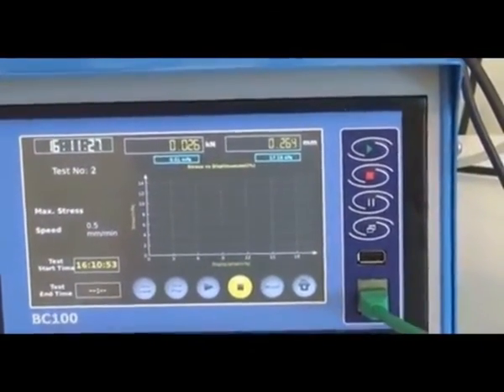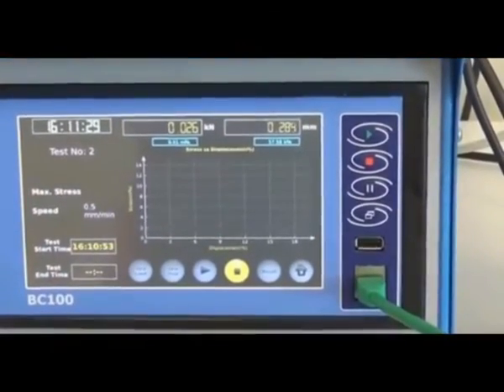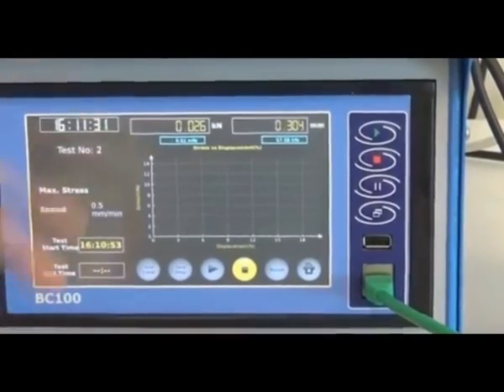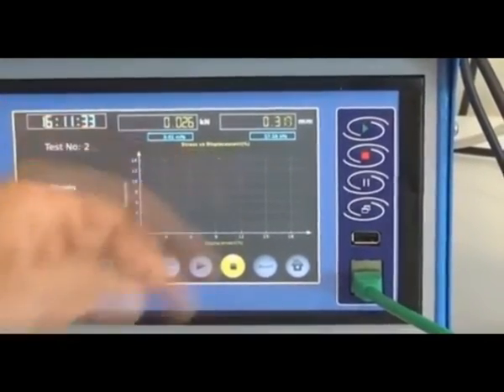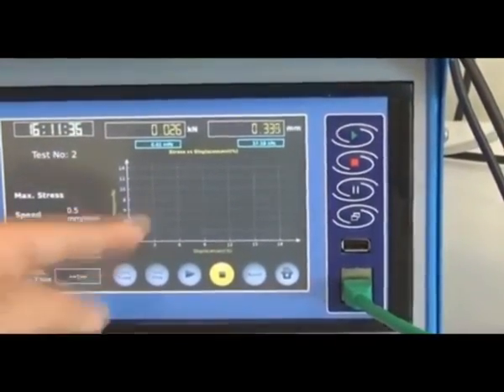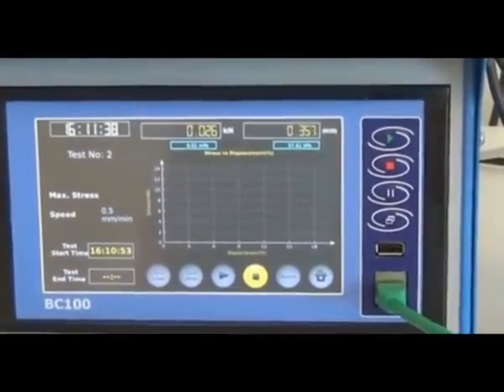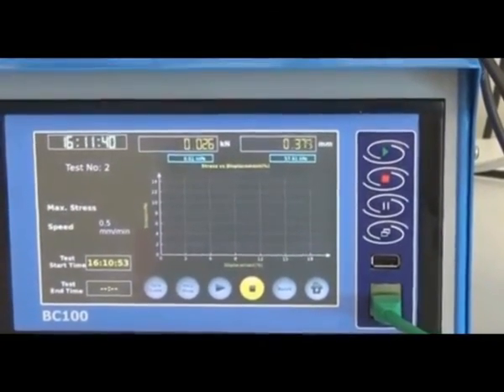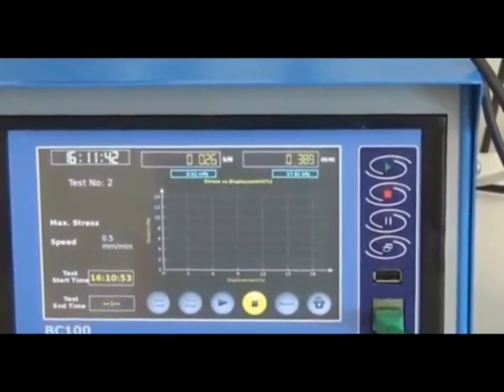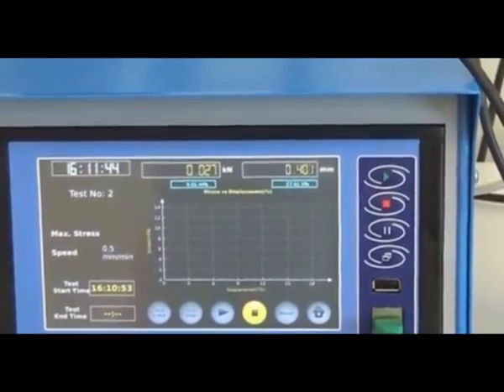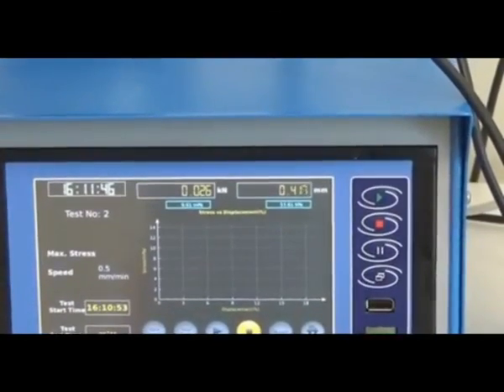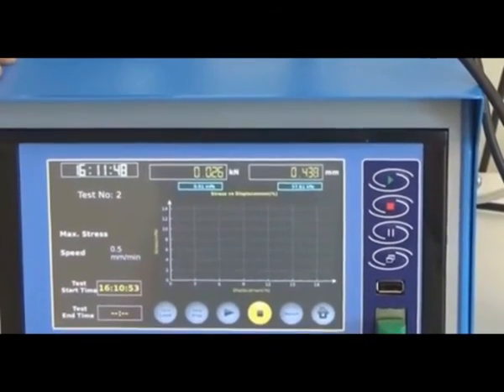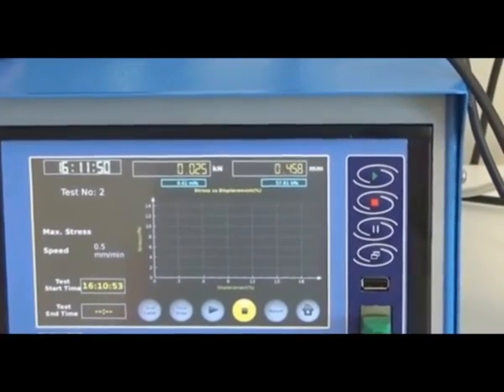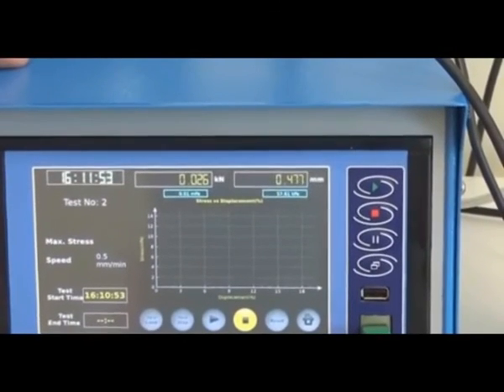As you can see here on the test screen, as the displacement increases, the stress versus displacement graph will be drawn onto this screen. And after 10% of axial displacement strain, the program will automatically detect the failure, stop the process, and give the results to the software program.